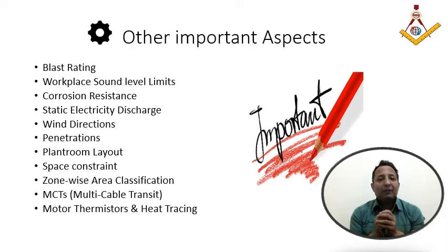It's a mechanical damper which is blast rated, and we need to give the blast rating to the equipment manufacturer. There are very few damper manufacturers who produce blast rated dampers. Normally the length of those dampers is almost 1 meter, so that they can mount all the arrangements, and there's a spring which can sense the sound pressure and it closes automatically after achieving that pressure. This is what the dampers are made up of. So this is the blast rating, and I'm going to cover it in much more detail in a later section, how it looks.